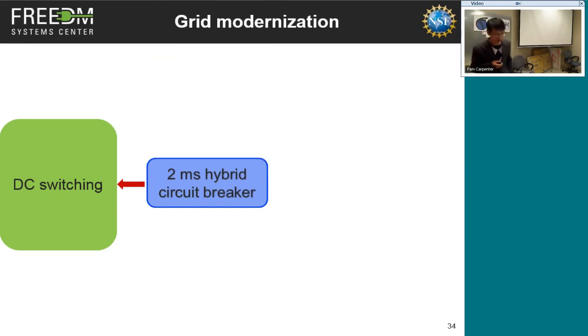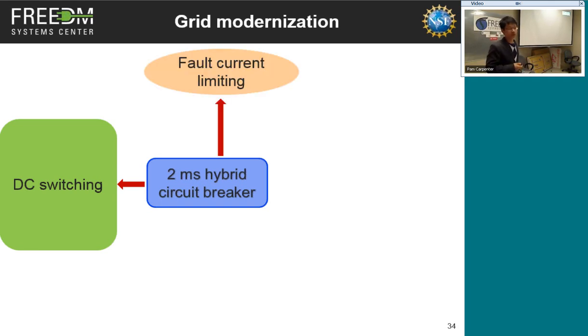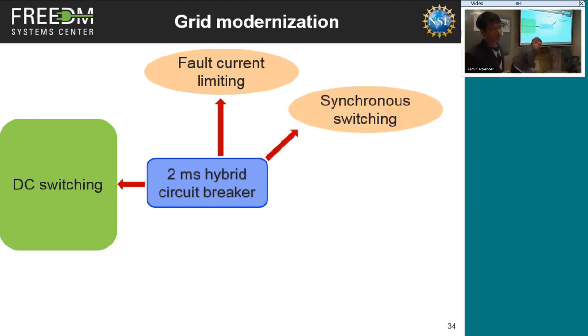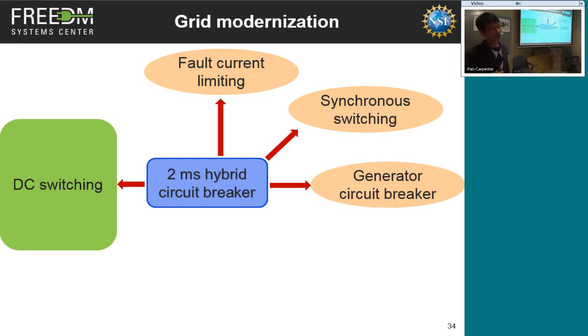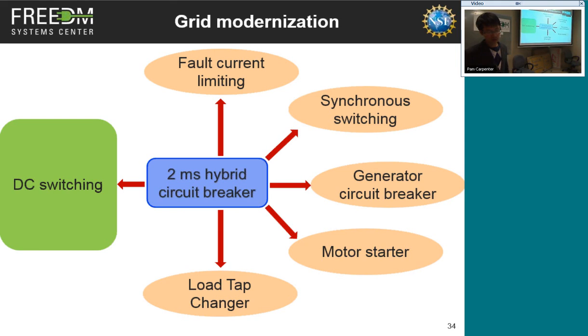We were talking about AC applications for these hybrid circuit breakers. We believe this hybrid circuit breaker should work in an AC system and should work even better than conventional AC circuit breakers, and I'll explain why. First of all, we can do fault current limiting, no problem, and we can do synchronous switching, and we can use it as a generator circuit breaker. We can use it as a motor starter, and we can also use it as a load tap changer. Those are all conventional AC applications.